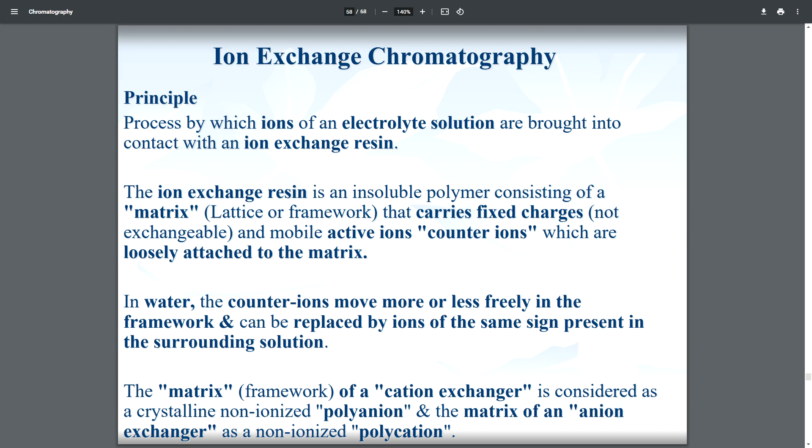The ion exchange resin is an insoluble polymer consisting of a matrix that carries fixed charges. These fixed charges are not exchangeable. The mobile active ions — counter ions — are loosely attached to the matrix. In water, the counter ions move more or less freely within the framework and can be replaced by ions of the same sign present in the surrounding solution.